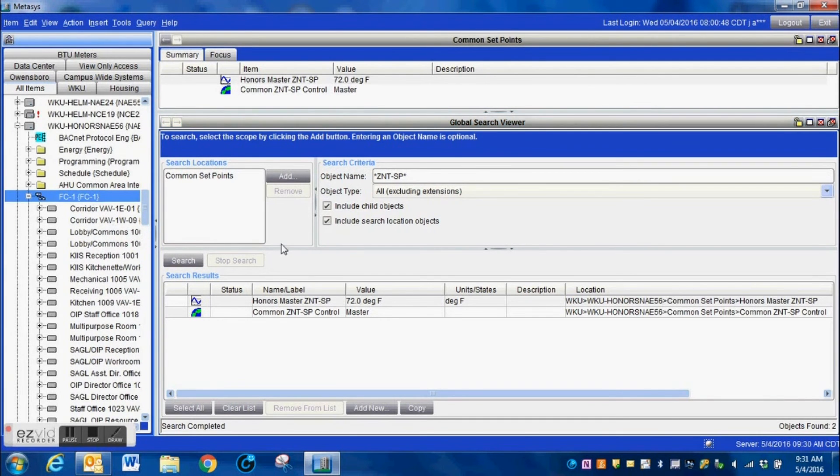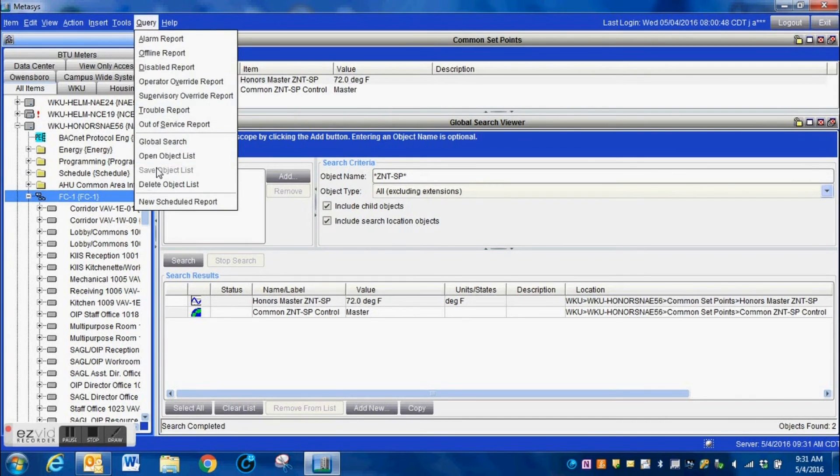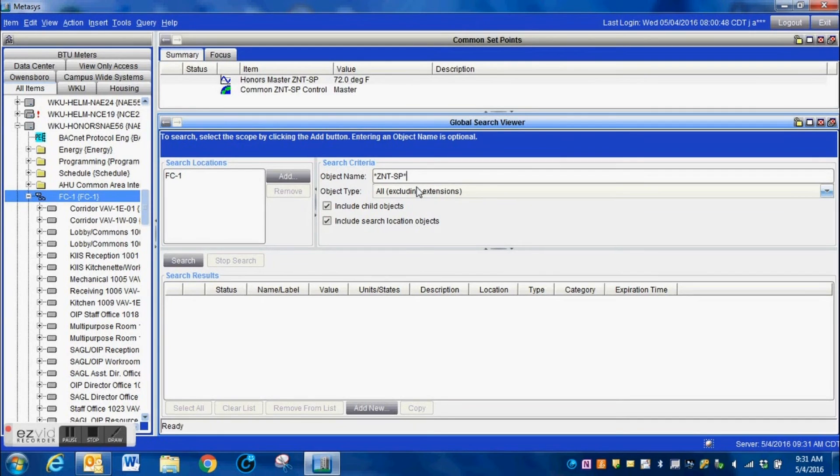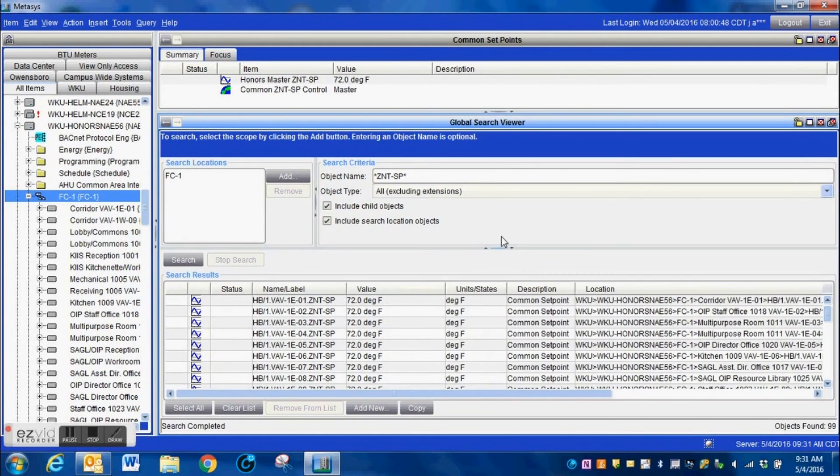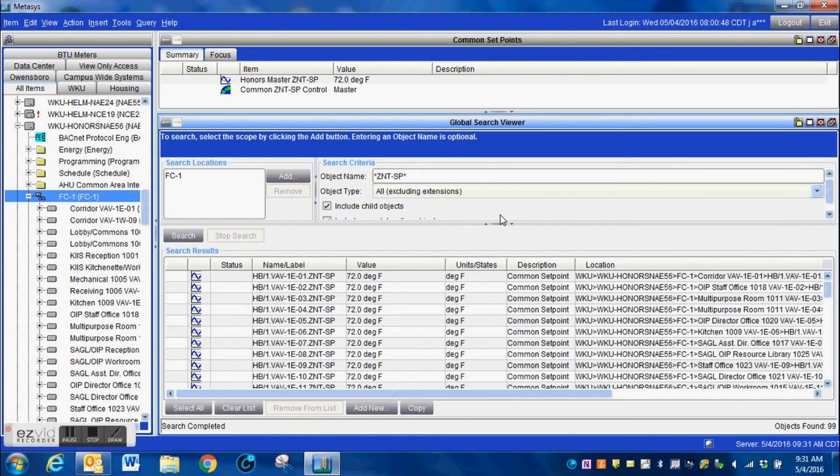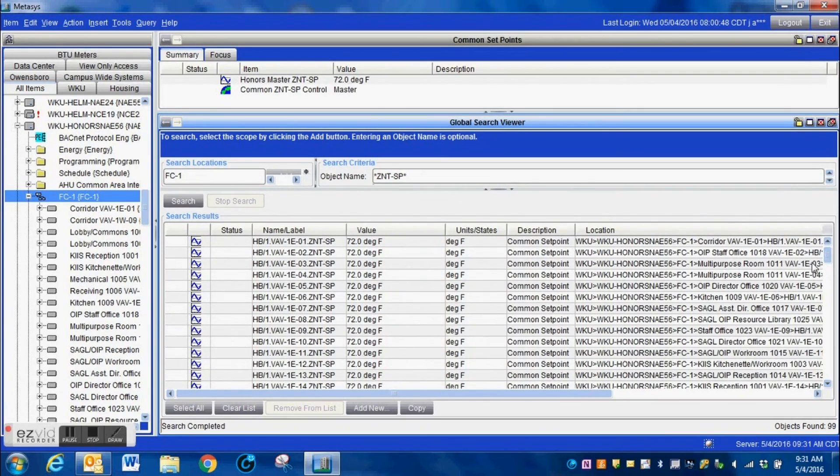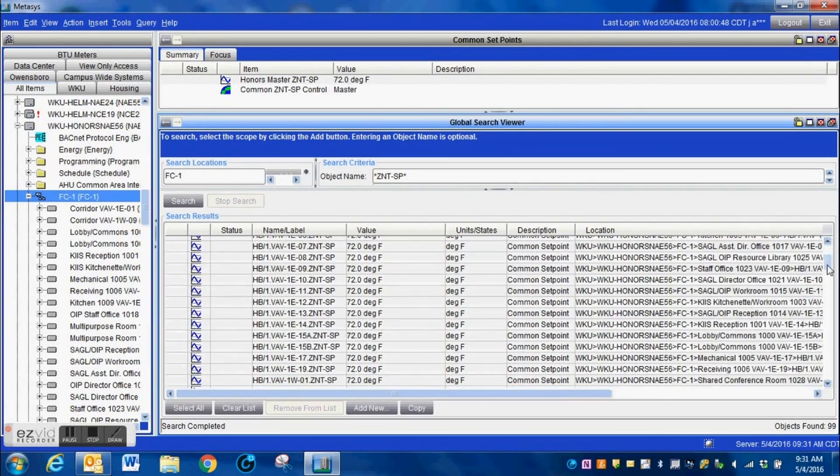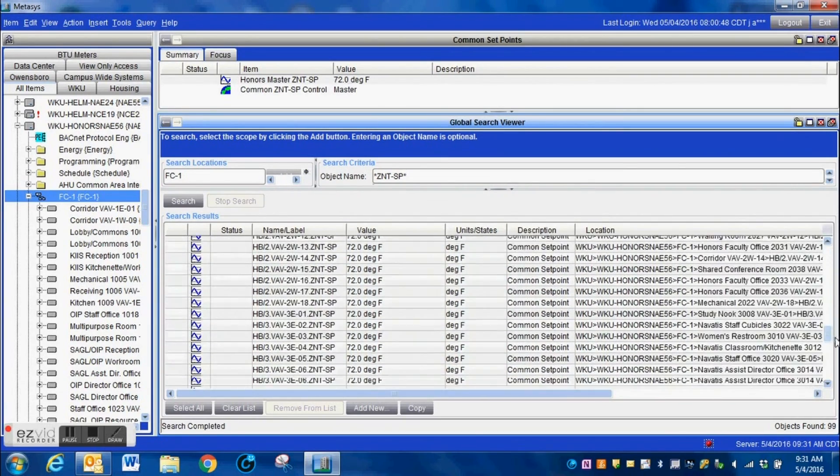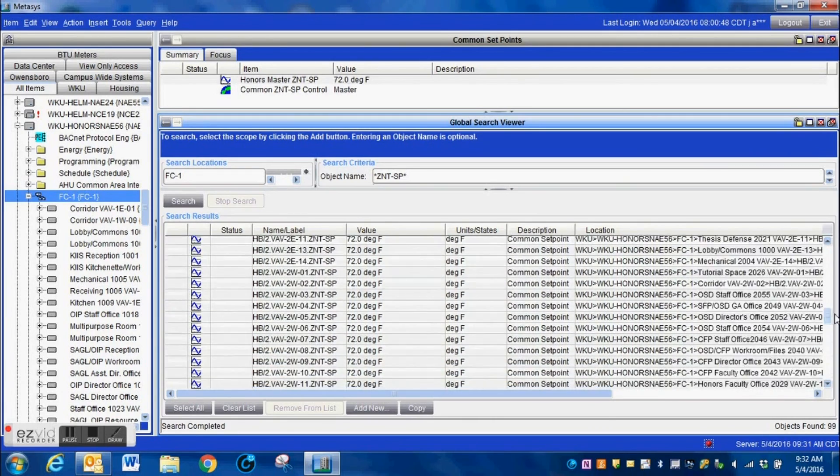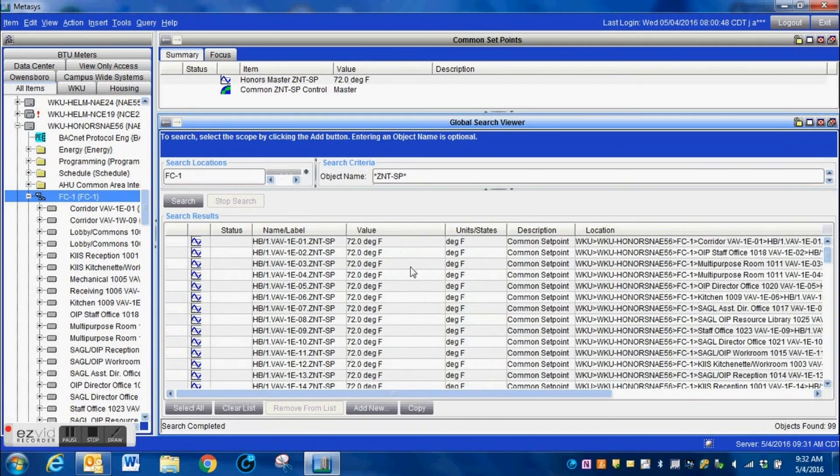But if you ever get into a situation where you were trying to figure out why a set point continues to change back or whatever, that may be it. That's a good possibility. That's what has happened. A global data has rebroadcast a value and it has changed a set point within your system. An override or whatever can lock it out. That's very simple to do as far as that goes. If you need to temporarily have one of your controllers different from the others, you can go back in and delete that from your logic block if necessary.